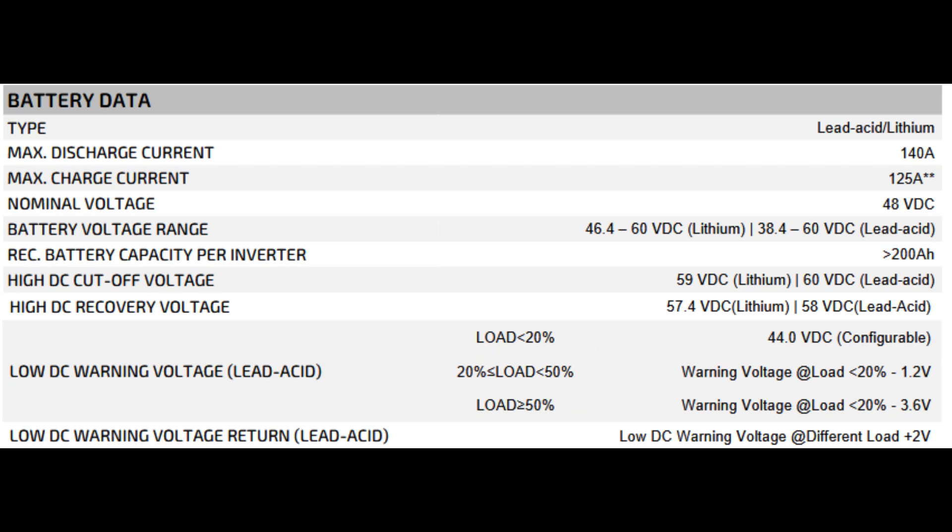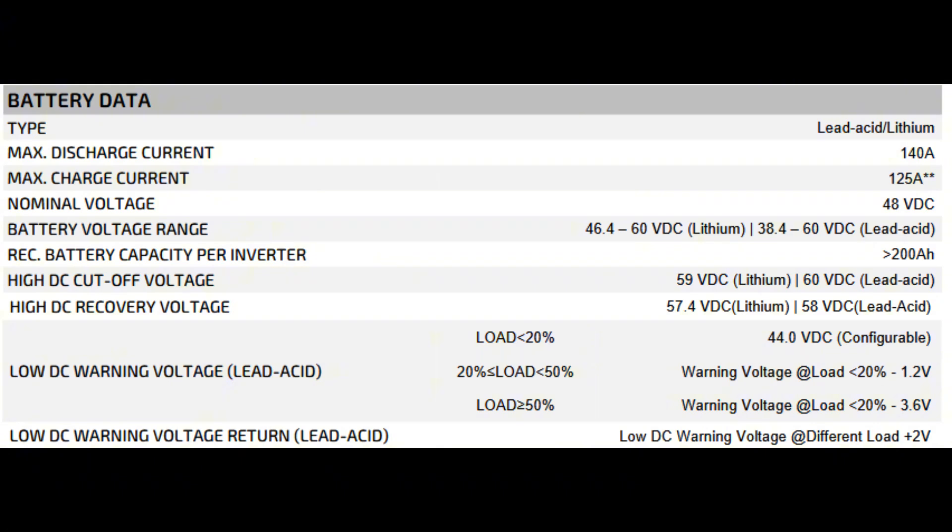It works with both lead acid and lithium chemistries, but lithium is where it really shines. 140 amp max discharge and 125 amp max charge means you can pull or push a substantial amount of current. Nominal 48 volts is pretty standard for modern off-grid and hybrid systems. They recommend at least 200 amp hours per inverter. I run 30 kilowatt hours worth of EG4 LLS lithium, so that's 600 amp hours total at 48 volts, more than enough to satisfy these requirements.